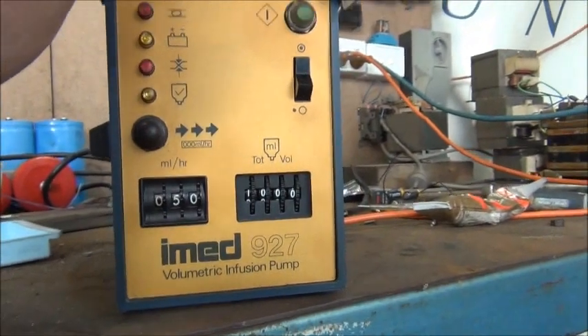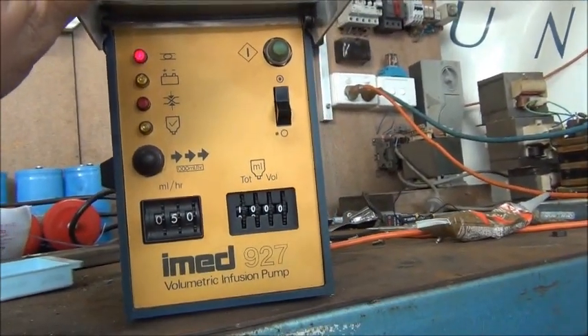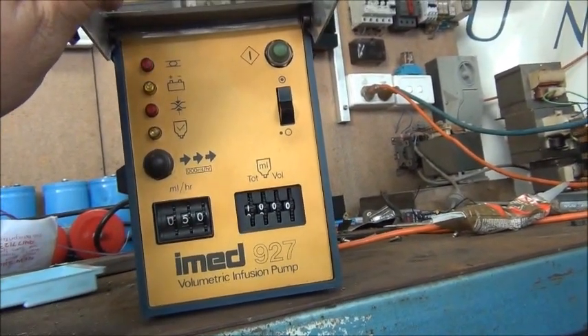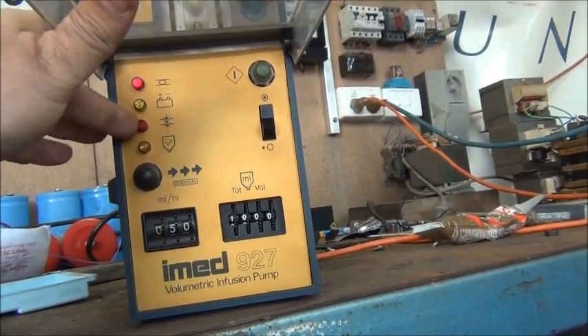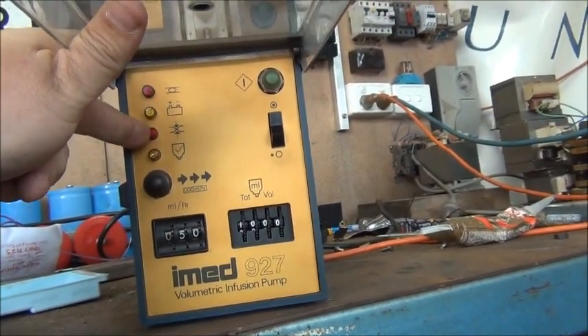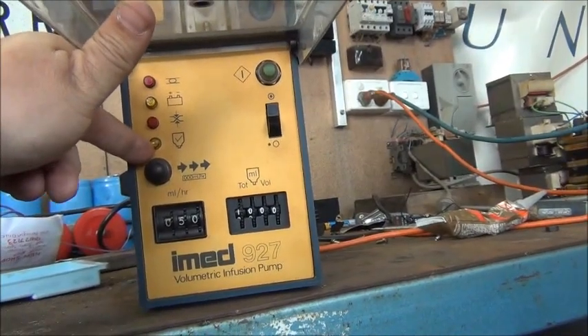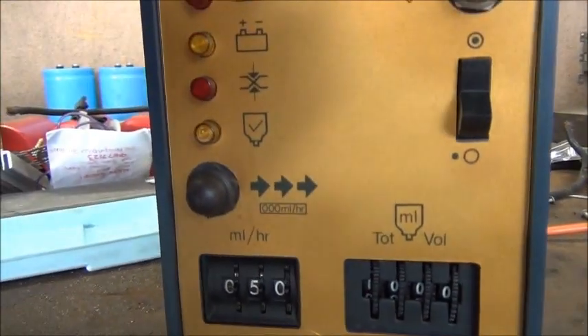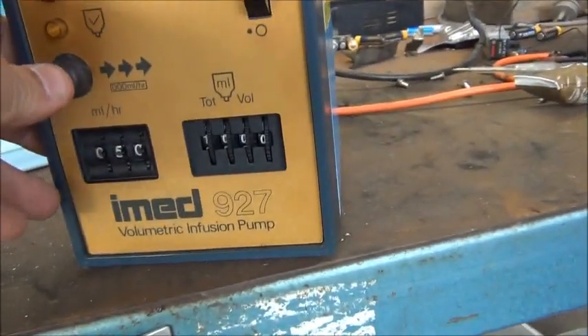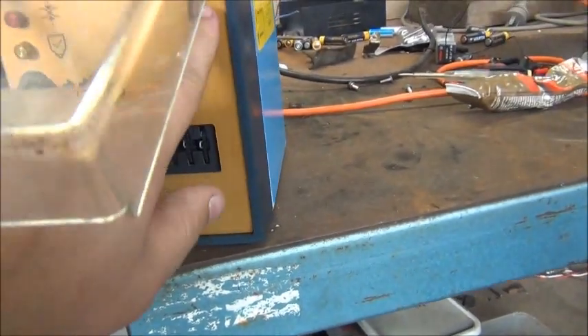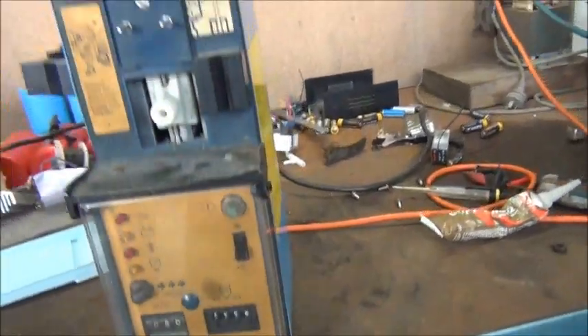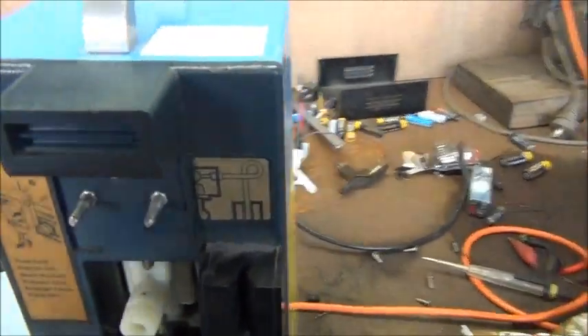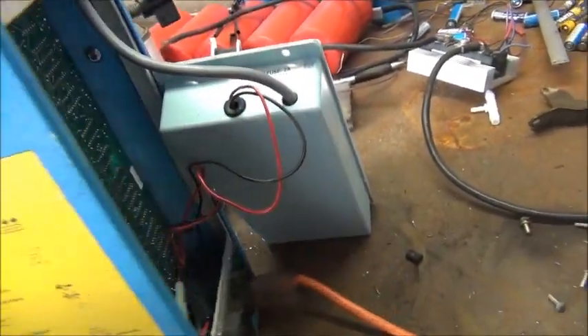Little control panel in the front. Some warning lights. It does tell you what they all are. Battery warning, air in line, so the line is blocked, it's got a crimp in it, and I think that one might be finished, I'm not sure. Yeah, infusion complete. That one's medicine finished being given. That's to bleed it. Main power, and obviously the start button. It's not happy because its cartridge is missing, the pump's missing, so I can't really run it.